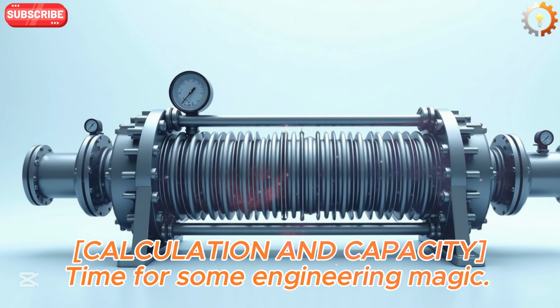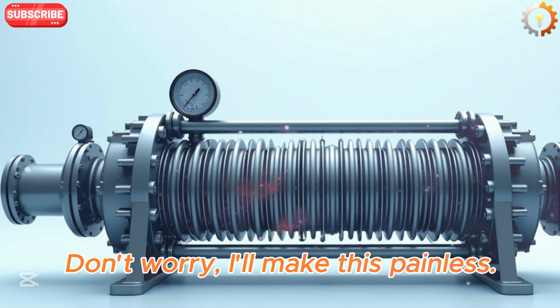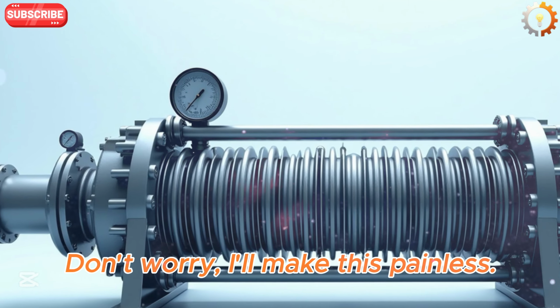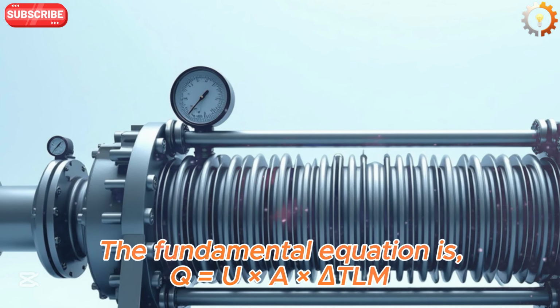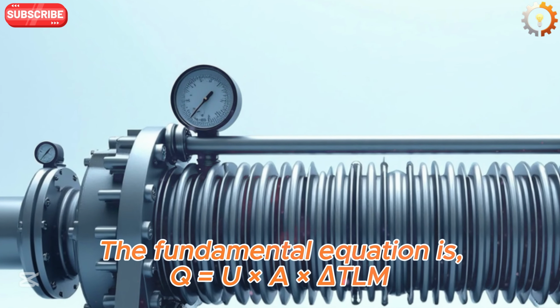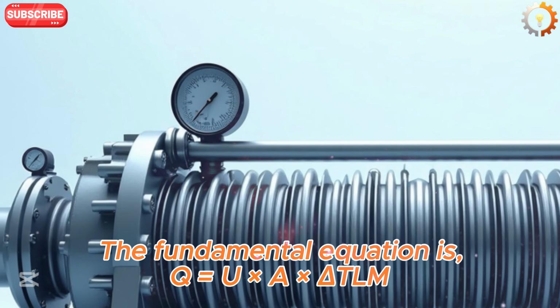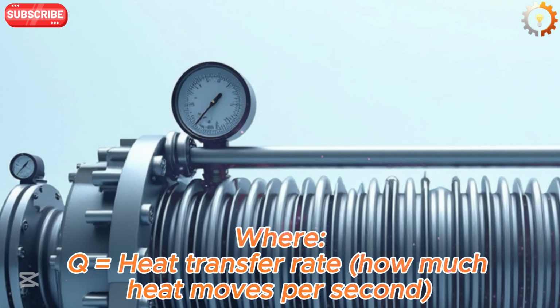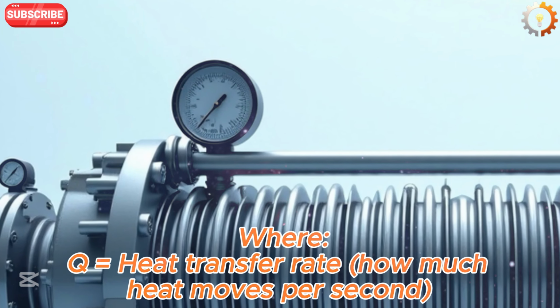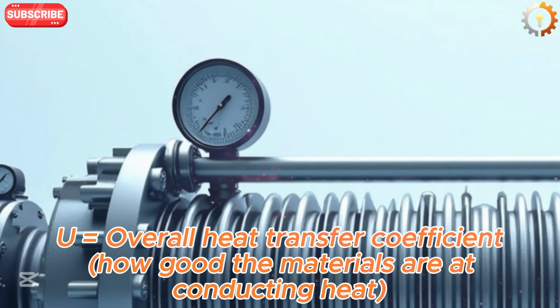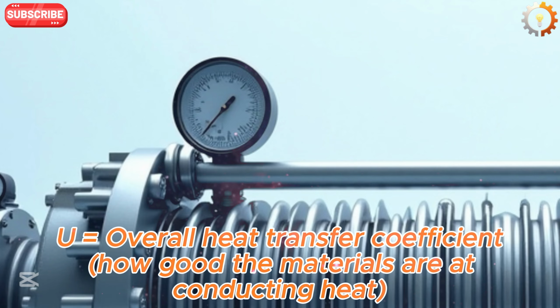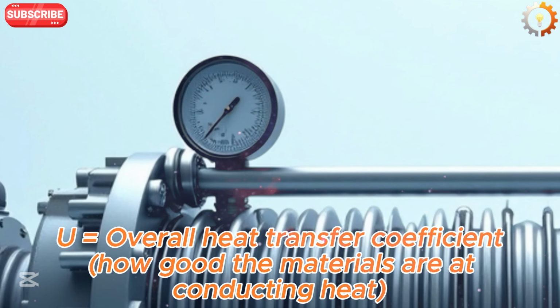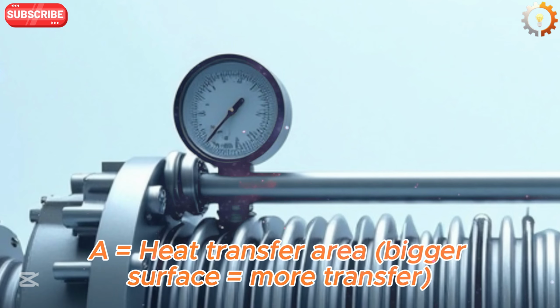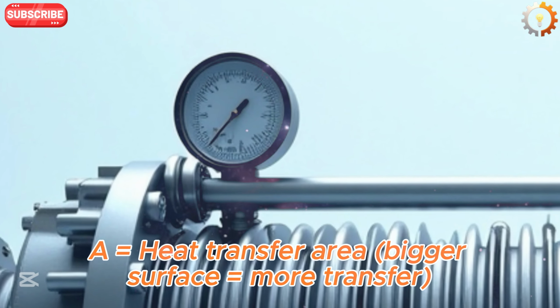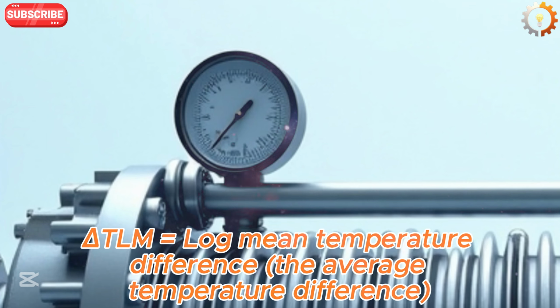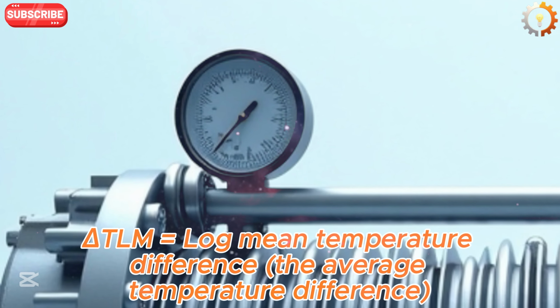Calculation and capacity. Time for some engineering magic, don't worry, I'll make this painless. The fundamental equation is Q equals U multiplied by A multiplied by delta T LM, where Q equals heat transfer rate, how much heat moves per second; U equals overall heat transfer coefficient, how good the materials are at conducting heat; A equals heat transfer area, bigger surface equals more transfer; and delta T LM equals log mean temperature difference, the average temperature difference.